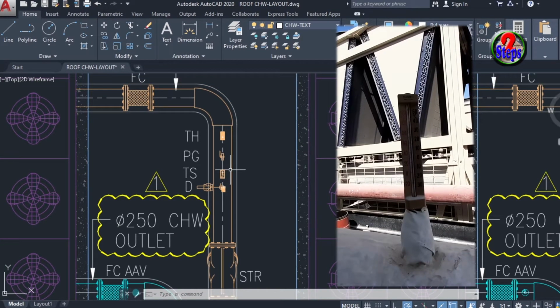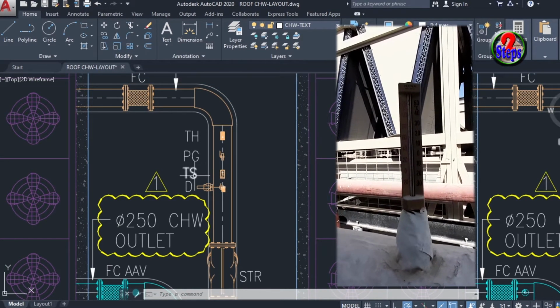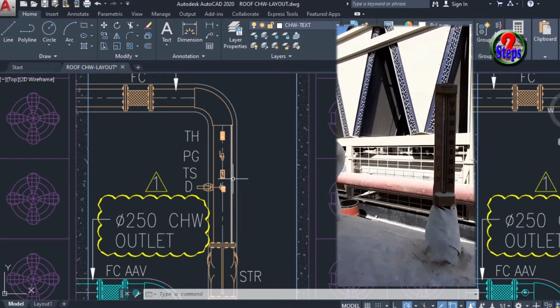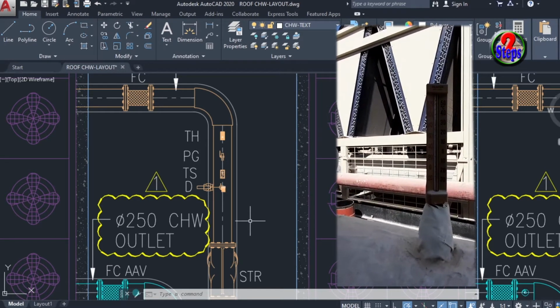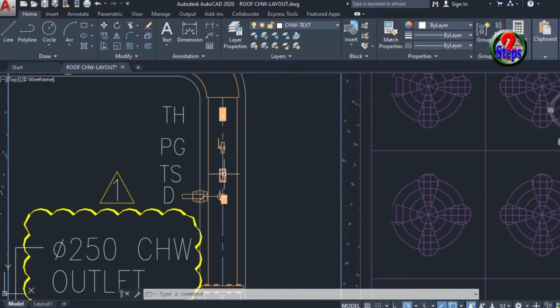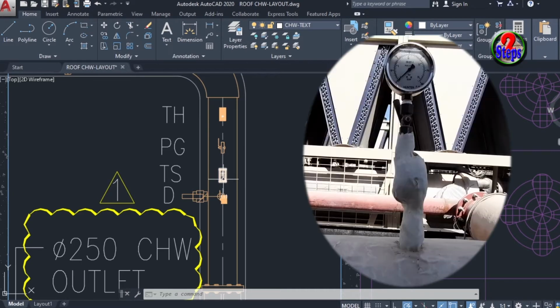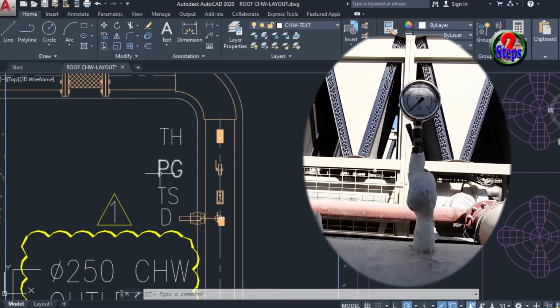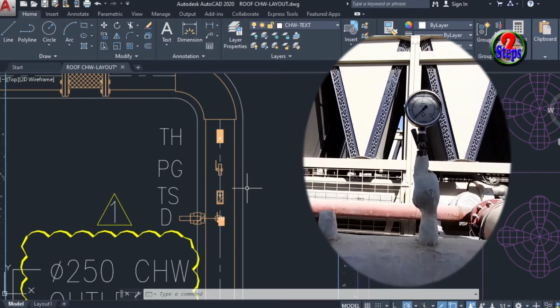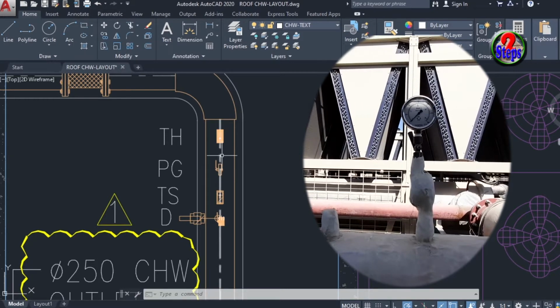After that, the temperature sensor point. The drawing symbol is TS. It's for measuring the pipe water temperature. Generally, the chiller inlet pipe water temperature is around 12 degrees Celsius. And then the pressure gauge point. The drawing symbol is PG. It's for measuring the water pressure inside the pipe.